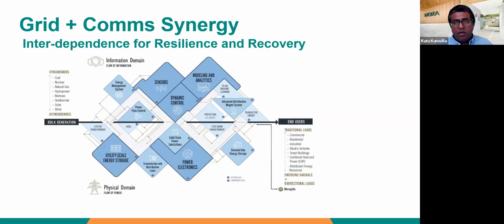So the energy management system of that farm went down, which caused the utility to lose visibility of that generation resource. The protocol had a direct transfer trip - typically if there's a fault on a generation system, the utility may trip it off the grid. Since there was no awareness of what was happening because the solar plant had lost its EMS system, the utility defaulted to a fail-safe and tripped that generation source.